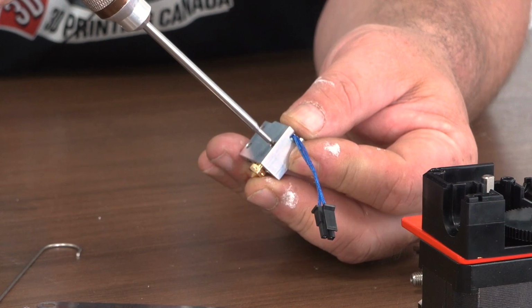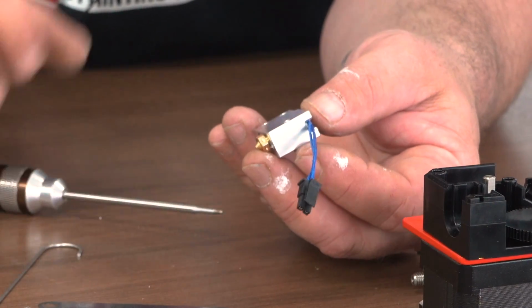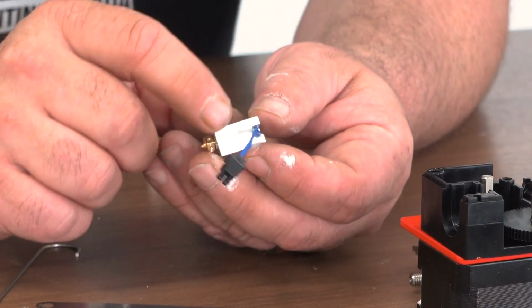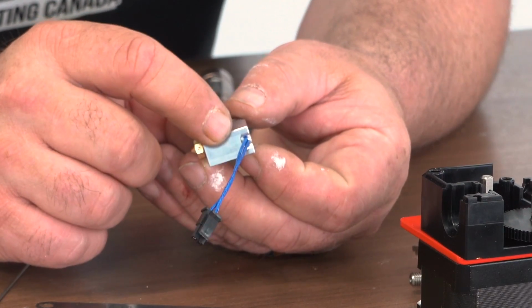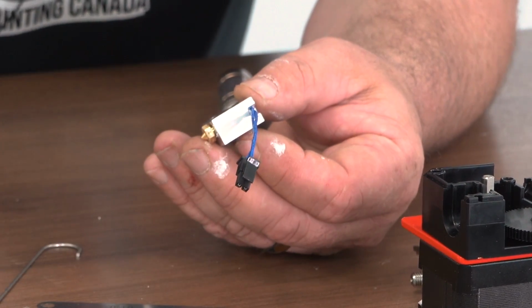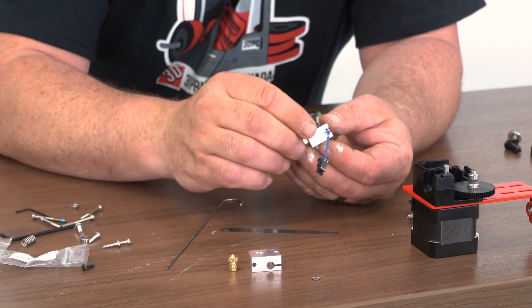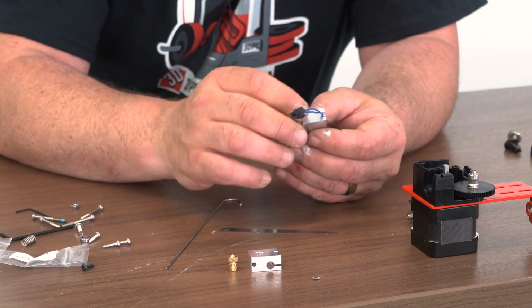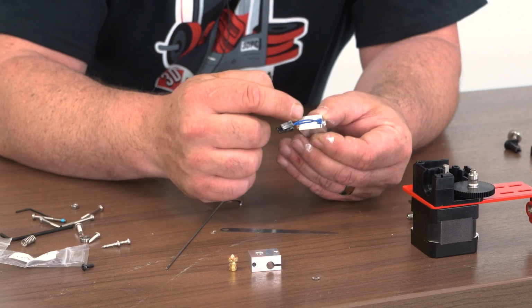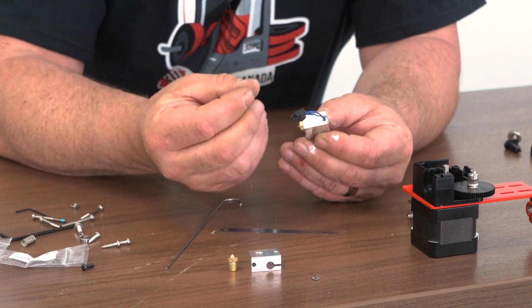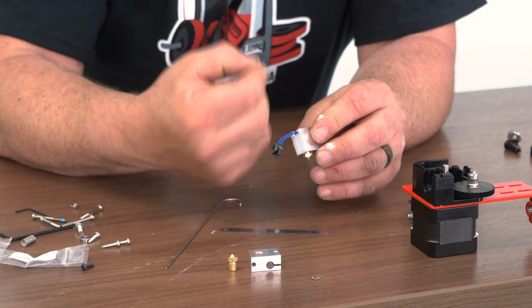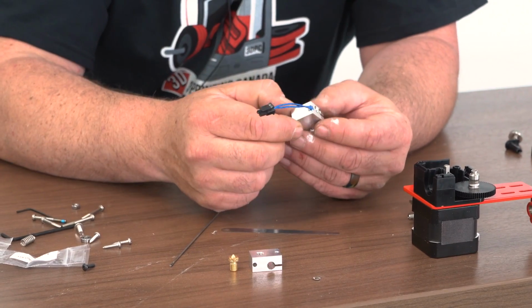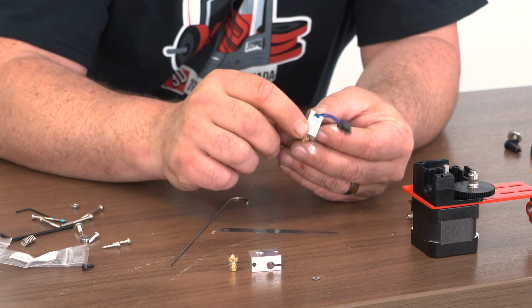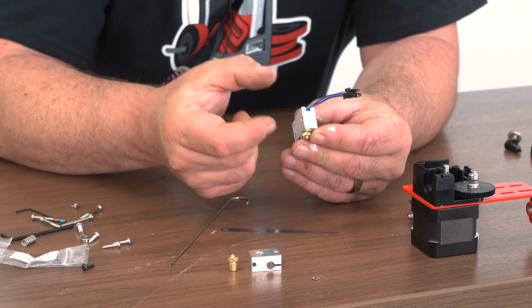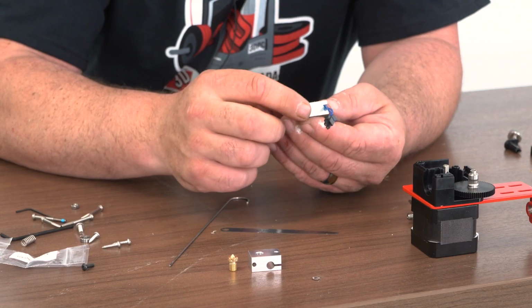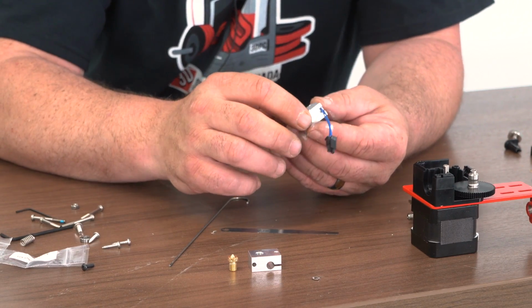Once I feel contact of that grub screw to the thermistor cartridge, I continue to tighten it about another quarter turn, that's it. Bear in mind that with this heater cartridge, you don't want to crush it, because if you crush or deform it, you'll never be able to get it out of the block and change it. You just want to tighten the grub screw down enough to hold it, without deforming it or preventing it from ever coming out.